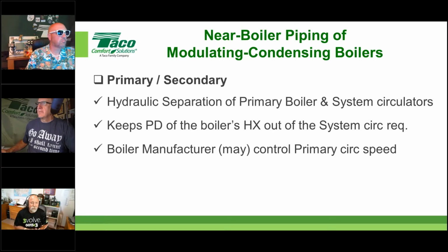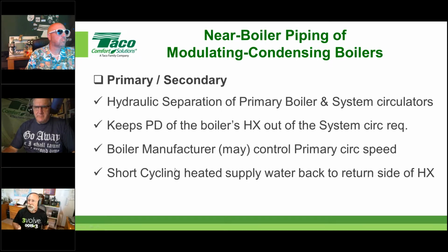Now, as mentioned already, when I showed you the little control wire coming down, some boiler manufacturers give you the ability to control the primary boiler circulator speed with an input, 0 to 10, pulse width modulation, or something like that. And again, check it out. If that's something that you have available, then look into it. And there's other ways around it as well. And for the sake of time, I won't get into that, but we'll spend some other time talking about what we could do to the boiler primary without having any signal and still get some variable speed there.